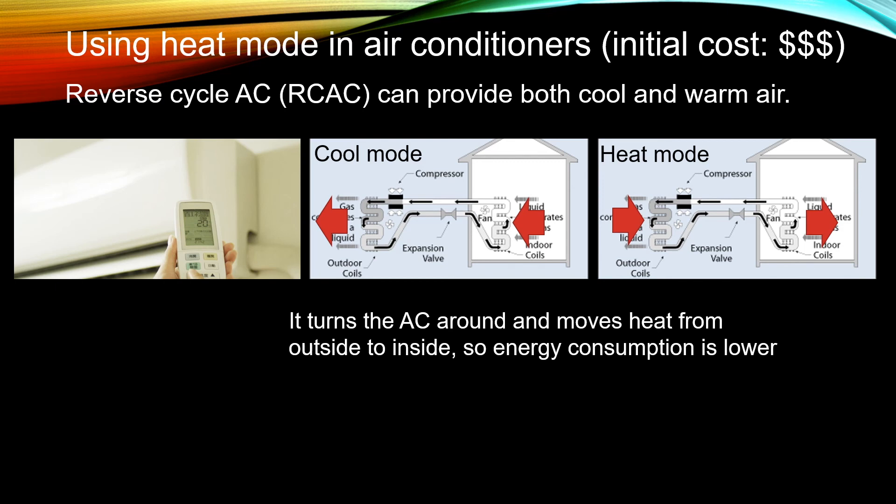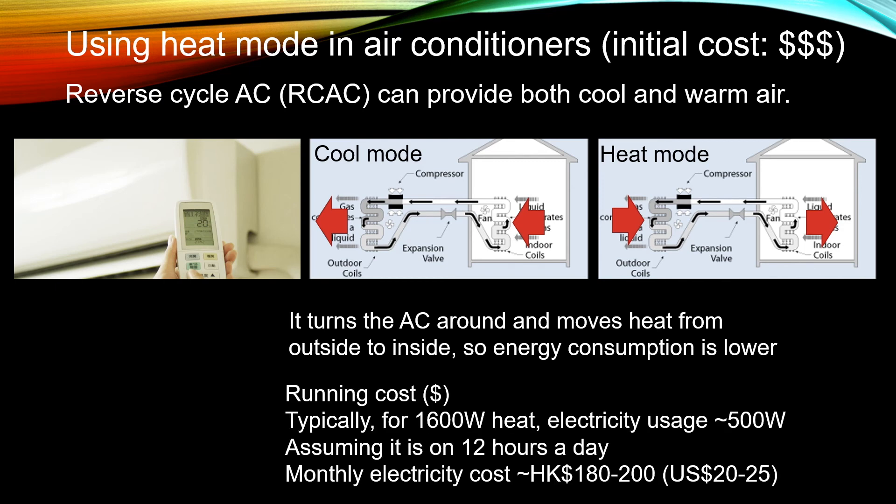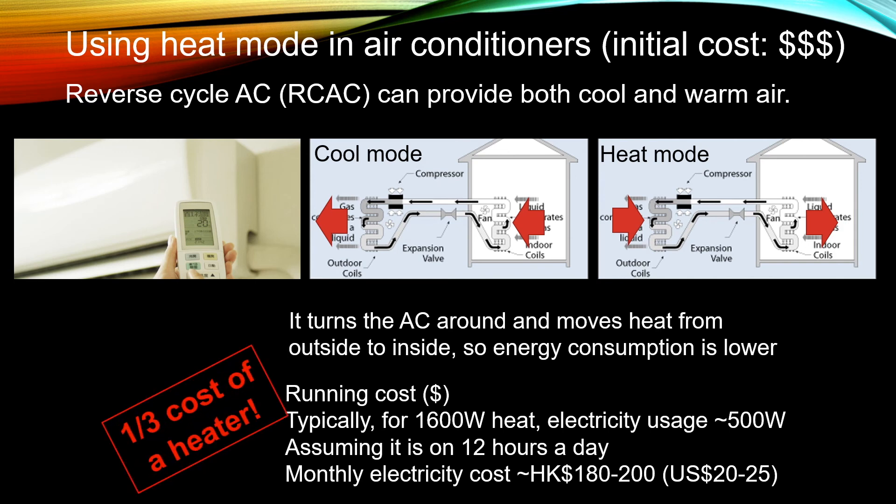Because you are moving the heat instead of generating the heat, the running cost is actually lower. If you want 1600W of heat, actually the electricity usage is only about 500W. So if you assume 12 hours a day of operation, the monthly electricity bill is only about 180 to 200 dollars. So it's one third of the cost of a heater.